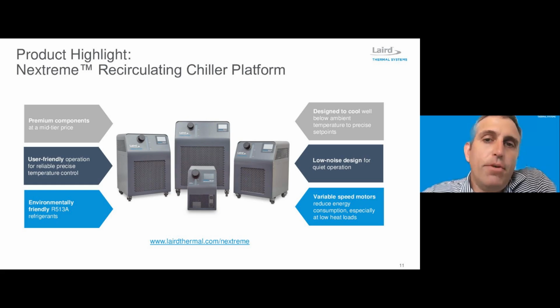Another feature that we've implemented into this product design is variable speed. We did this on the compressor and the condenser fan. We did this specifically on those two motors because that's where the performance of the system varies the most. The customer always has a need for constant flow rate, so putting design and cost into variable speed on the pump motor wasn't as important to us as it is on the compressor. These systems often will be in a standby state where they're cooling a very low load for extended periods of time and then called into action where they need to cool at 90%.